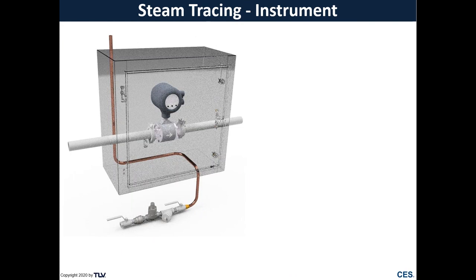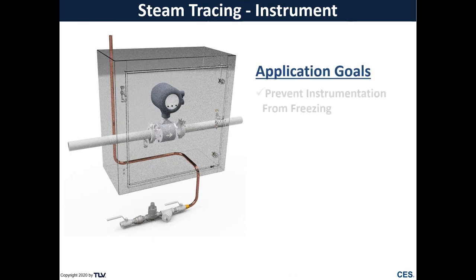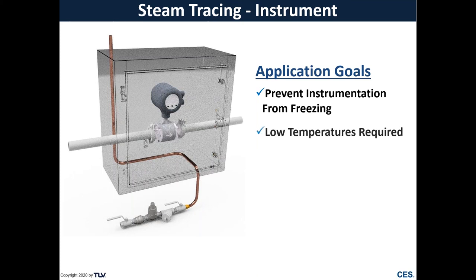Another type of tracing is what we would consider instrumentation tracing. So the goal here is to prevent that instrumentation from freezing. This is either a flow meter or analyzer or any other type of instrumentation that in cold climate may not operate properly if it gets too cool. So we have a very low temperature requirement, but if we have high heat provided to that instrumentation, we may damage it. So we want to be very careful not to provide too much heat to this application.